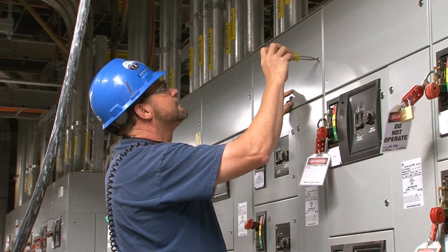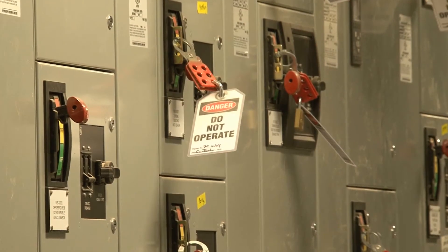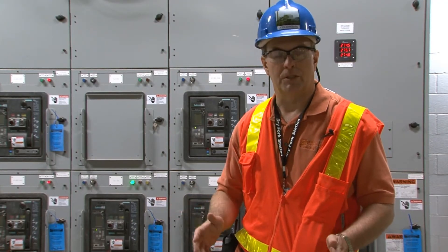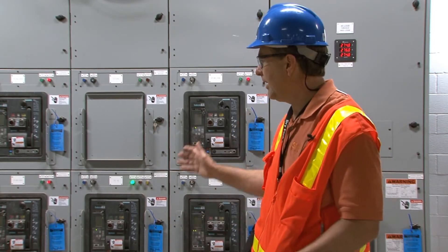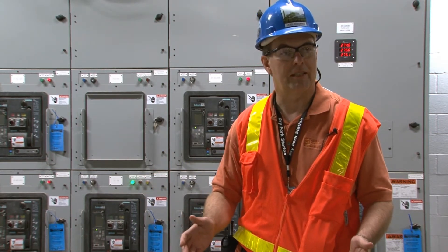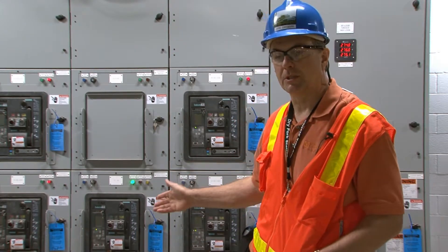Dingman says the blue tags are important for coordinating schedules between contractors and Basin Electric employees, and for safety. There's still a lot of buckets in the motor control centers that are not completed, so it's important that we maintain control of the equipment — the feed from this to there — so that contractors can continue to work on that portion of the system, and yet we can commission this portion.